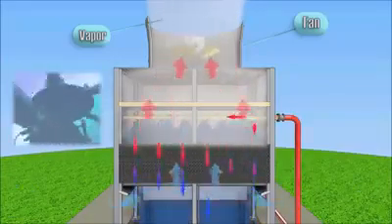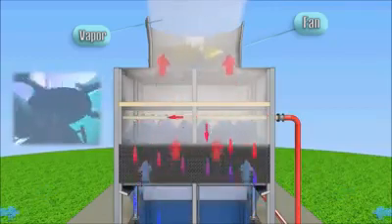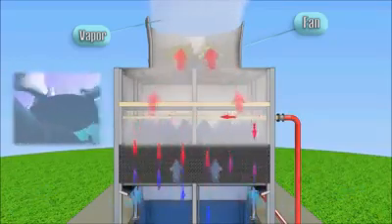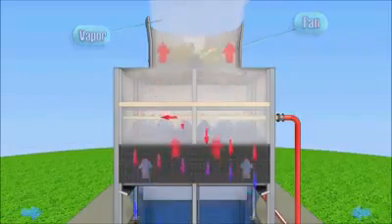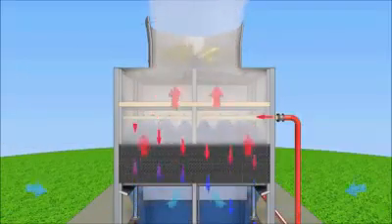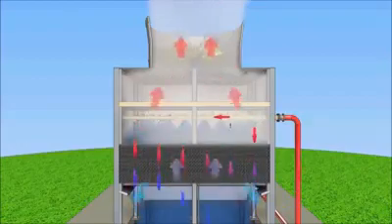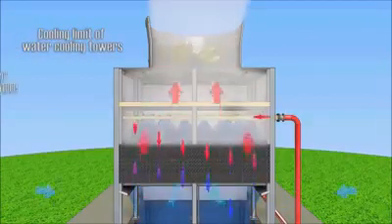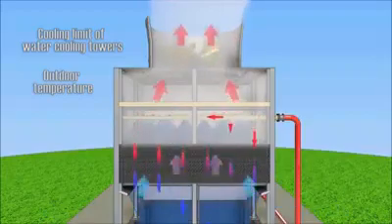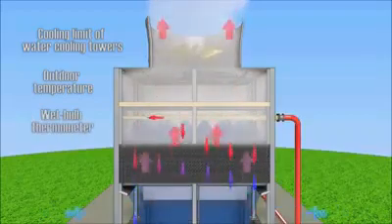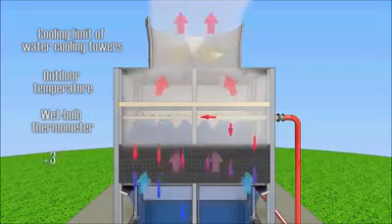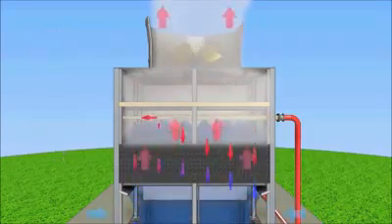The water cooling efficiency of the fan cooling towers may be controlled by varying the supply of air by the fans, changing the fan speed. Theoretically, the ideal loss is the work to convert the water to steam. The limit of cooling water in the cooling tower is the outside air wet bulb temperature. In practice, the limit of cooling is the wet bulb temperature plus 3 degrees Celsius.